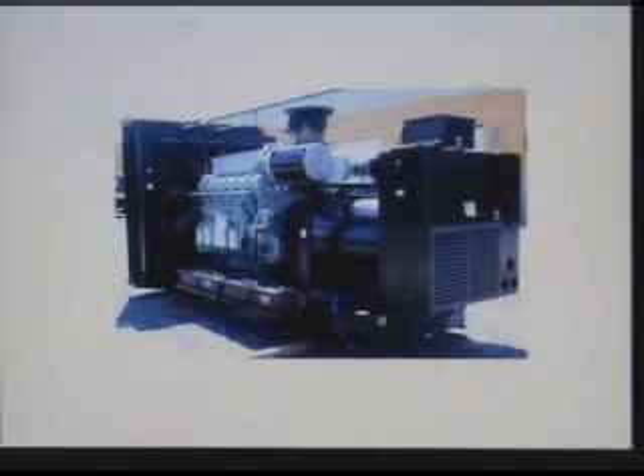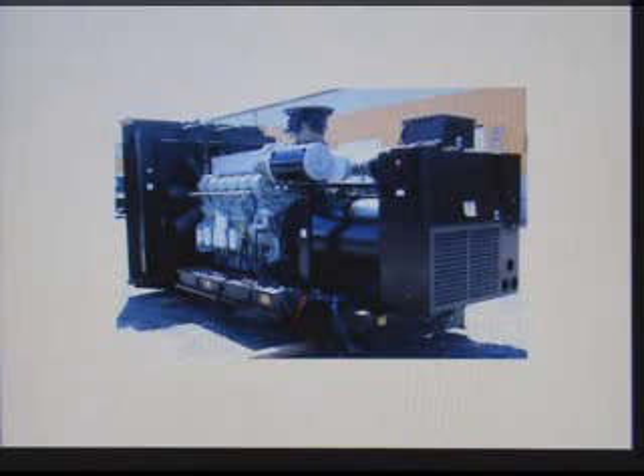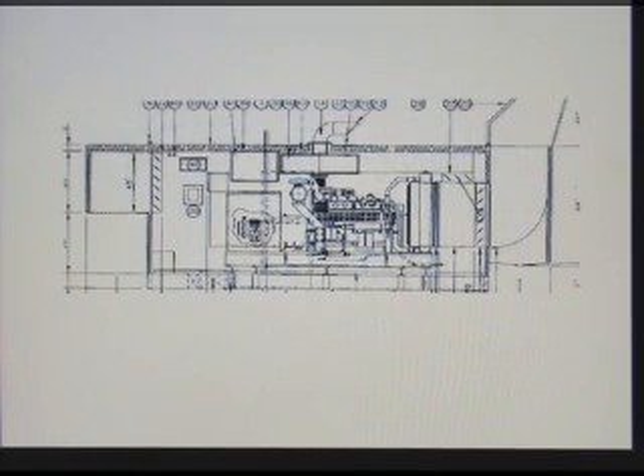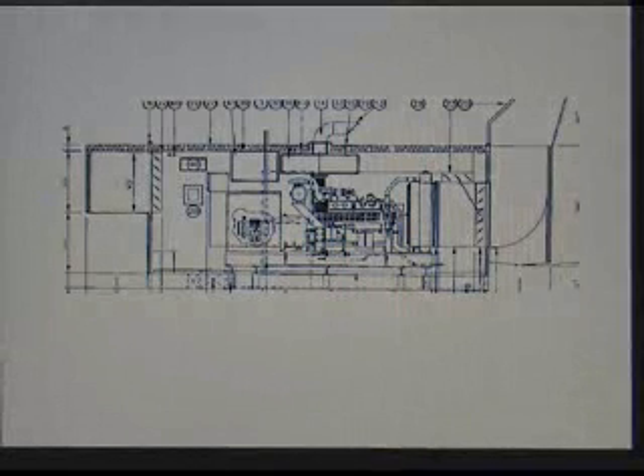So this is what you're going to look at when you get a package like this. You'll have the engine with a set of air filters just upstream of the turbos. You'll have a big radiator for cooling the water that cools the engine. And the generator will be attached, directly coupled to the engine with a small control panel and a terminal box for the electrical wires to be connected to take the power away. Generally, we buy them inside an enclosure because they're fairly noisy little animals, and we can't meet the 85 dBA noise requirements that OSHA has for occupied areas without an enclosure.